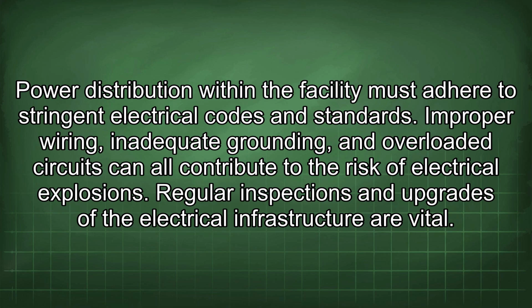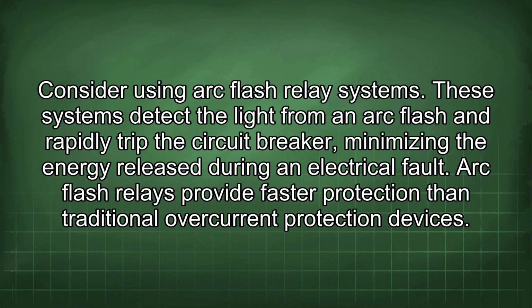Power distribution within the facility must adhere to stringent electrical codes and standards. Improper wiring, inadequate grounding, and overloaded circuits can all contribute to the risk of electrical explosions. Regular inspections and upgrades of the electrical infrastructure are vital. Consider using arc flash relay systems. These systems detect the light from an arc flash and rapidly trip the circuit breaker, minimizing the energy released during an electrical fault. Arc flash relays provide faster protection than traditional overcurrent protection devices.